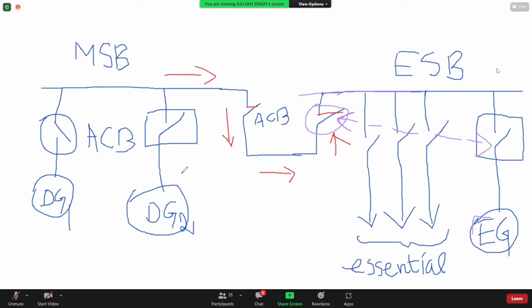Second thing done. Colors: red, yellow, blue. If you see red, yellow, blue, it is a line voltage, particularly going to some motor or big heater or some big load. It is going to some galley or it is going to the bridge. These are the three phases, with names RYB, RST, L1, L2, L3, phase 1, phase 2, phase 3. Colors: neutral black, ground green. Thereafter, we understood the ratio root 3. Line voltage is root 3 times the phase voltage.